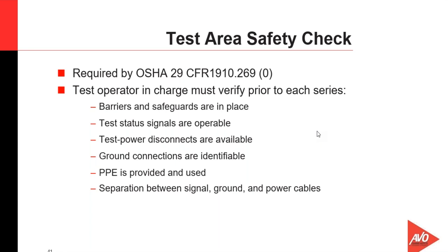We have all the barriers and safeguards in place. Test area status signals, if they're being used, and some companies use flashing light high voltage test signals, and in some facilities they have test cages and high voltage test areas that have flashing signals as well. The test area power disconnects are available. We know where they are, and they're available to the test technician that would need to de-energize the test area.